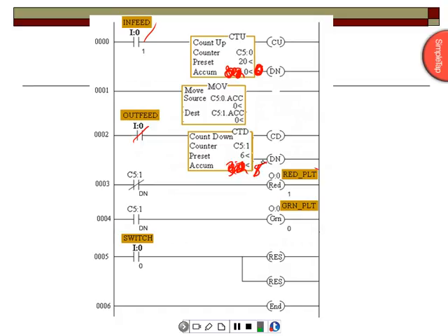So it takes the 5 and drops it back to 4. So it's just saying, okay, I'm gonna take these that come on here, move them over here. And then every time somebody breaks that beam and takes one off this conveyor, it's gonna drop it down one. So if I look at this accumulator register, I can always know how many is on that conveyor.